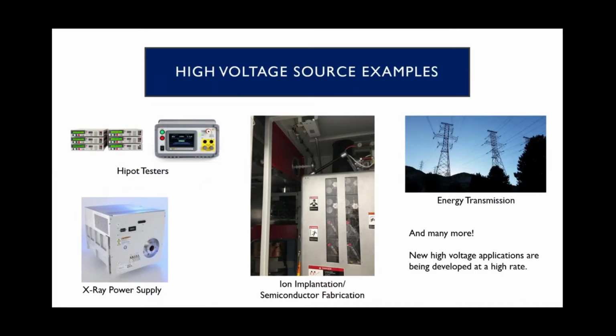So to go through a few real world examples which may need to have their high voltages measured, calibrated, or monitored, you have hipot testers, something that we're very familiar with here at Vitrek, which will output a high voltage into a device in order to ensure safety of that device.